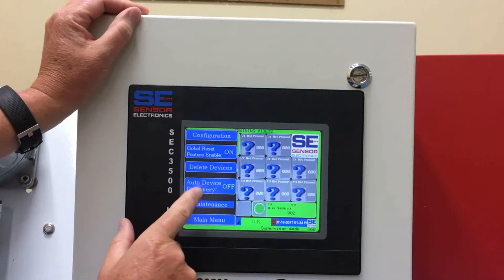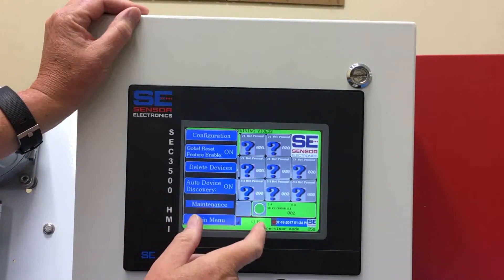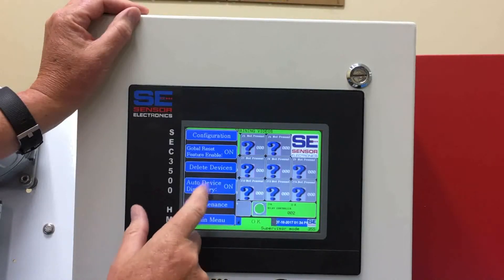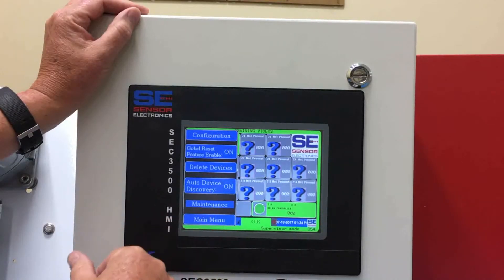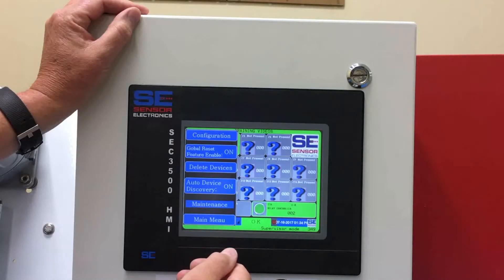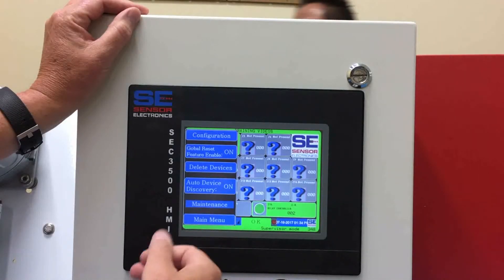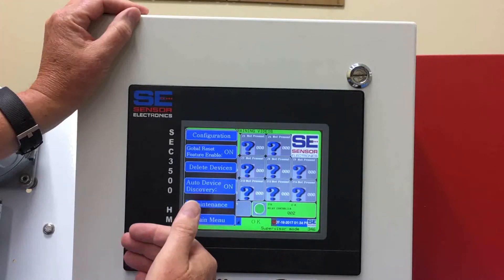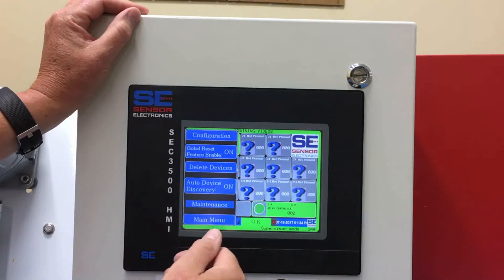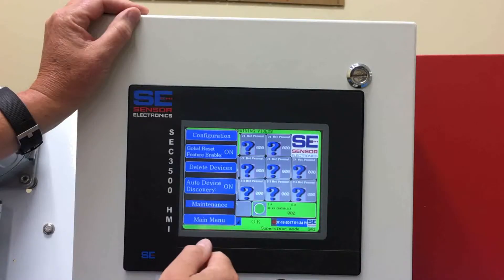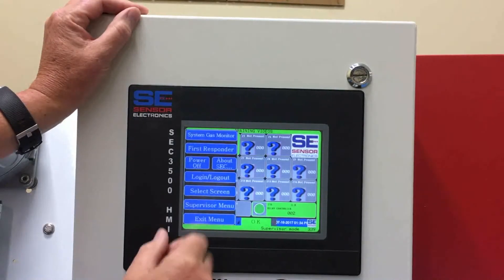Auto discovery can be enabled by pressing the button either on or off. When it's on, the HMI panel is continuously looking for new gas detectors on the system. So if you add gas detectors to the system, it's going to automatically pick them up — you don't have to go back and manually search for those detectors.